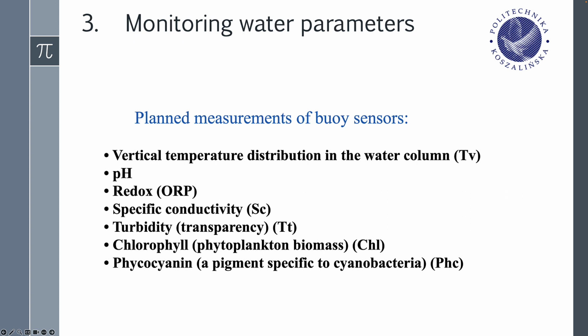The measurement is carried out using an integrated circuit that generates a variable voltage applied to metal electrodes. Depending on the electrolyte concentration, as the ion content increases, the resistance decreases, and the current intensity increases, greater conductivity. The higher the conductivity indication, indicating a larger dissolved substance load in the water. Turbidity, transparency, TT.